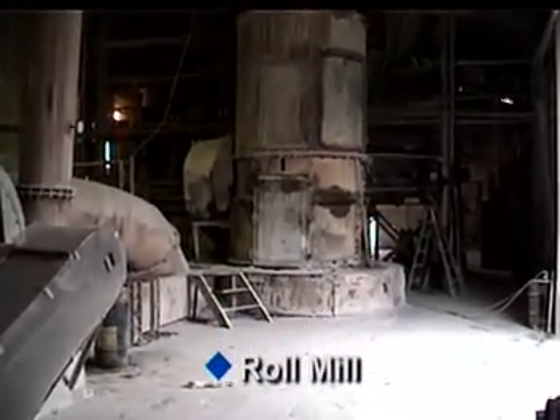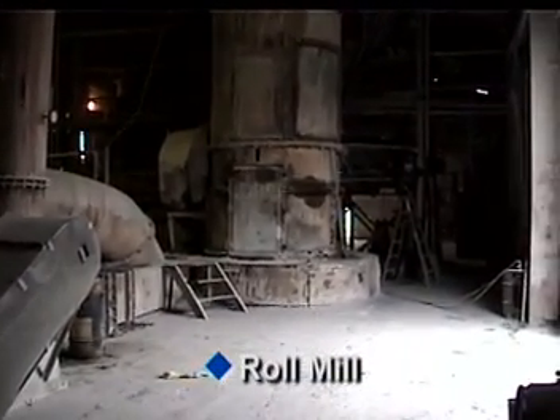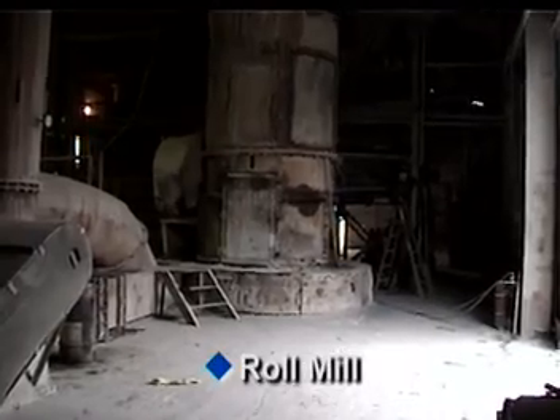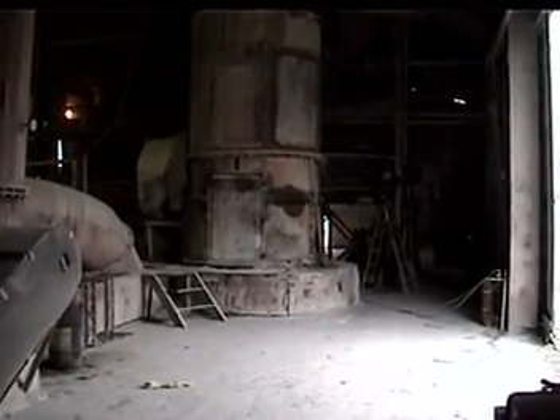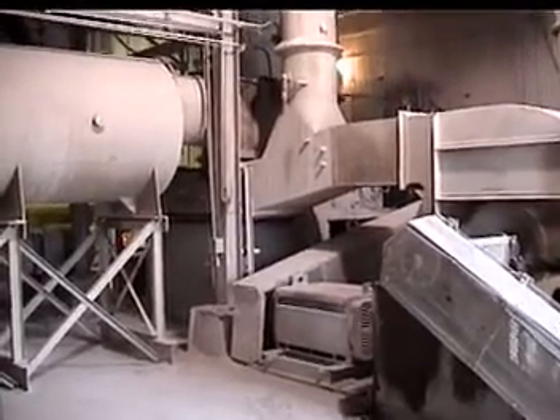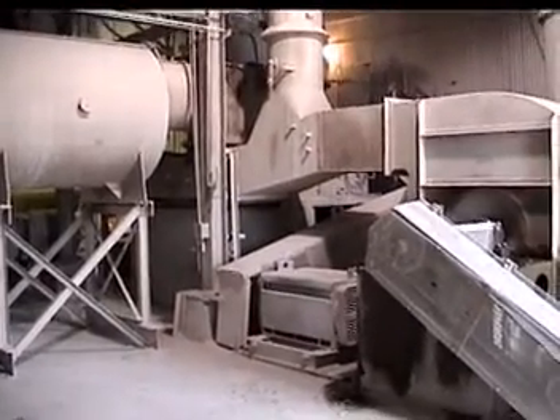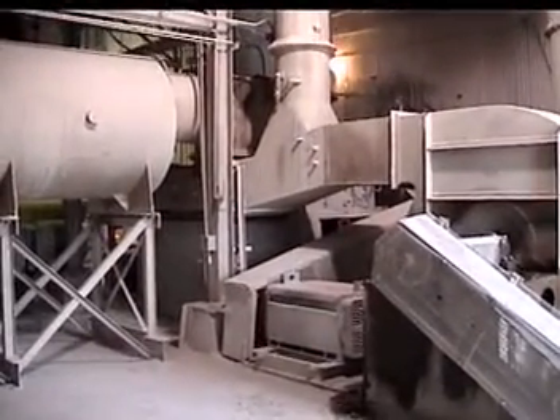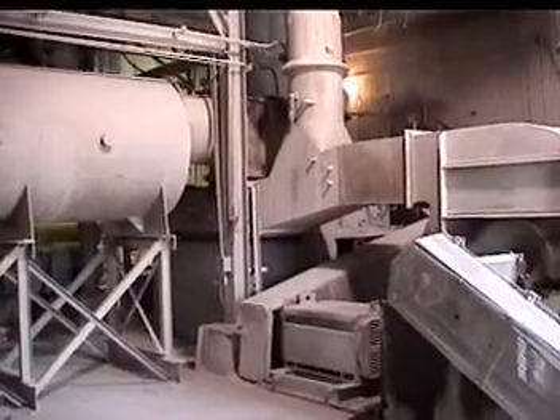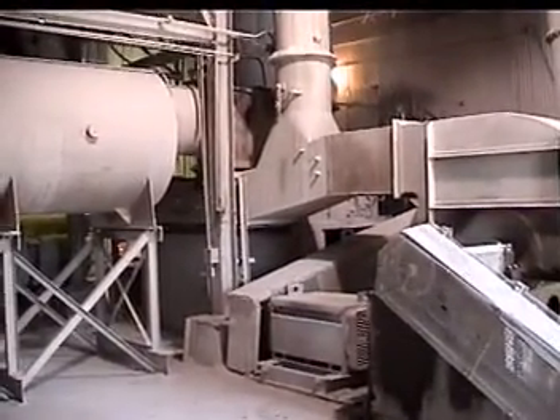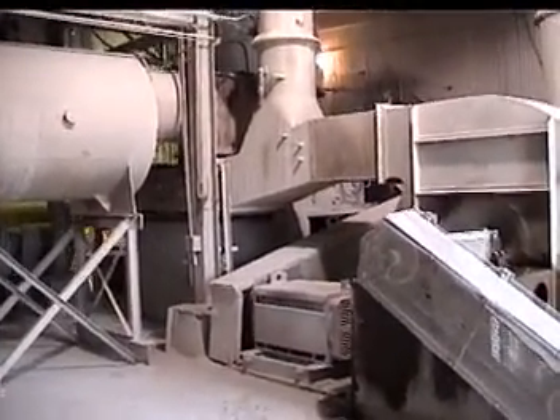This lime pulverizing roll mill is driven by a 400 horsepower induction motor controlled by a NEMA 12 400 horsepower combination solid-state soft starter, controlling inrush currents while eliminating mechanical shock. This unit can also provide jogging capability at 7 and 14% of motor base speed for maintenance inspection.